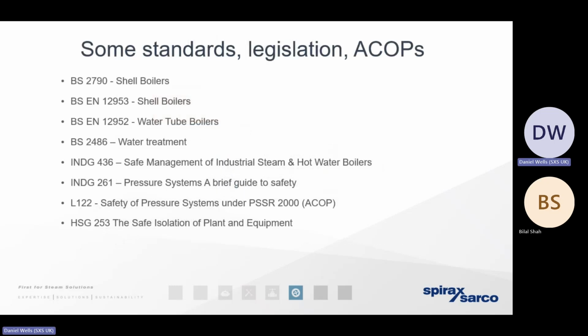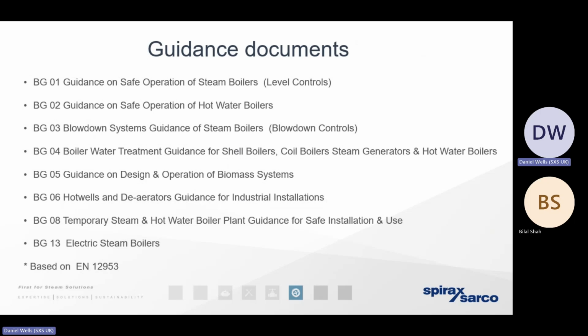So when we're talking to a steam using client, they've got a lot of responsibilities to ensure that their boiler house is operating in accordance with the appropriate standards. For me personally, INDG 436 is the important one. INDG 436, think of it as a risk assessment. So that helps our steam using clients understand what their responsibilities and obligations are in order to keep that boiler operating safely. Now, underneath that standard, there's a series of guidance documents. We call them the BGs. And these are written and administered by the Combustion Engineers Association in accordance with the Boiler Operators Accreditation Scheme, with oversight of the Health and Safety Executive.